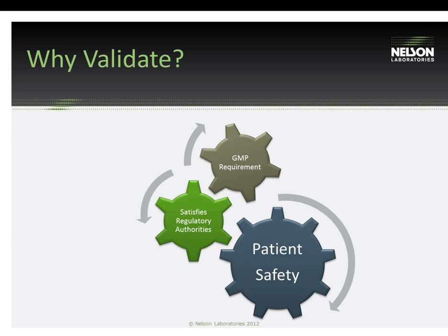And interestingly enough, that oil and those devices were showing up as not having a cytotoxic effect. And so again, kind of going along with that concept of just because something is sterile and non-cytotoxic does not mean it's clean. And so the effect to the function of the device should also be examined with these cleaning validations.